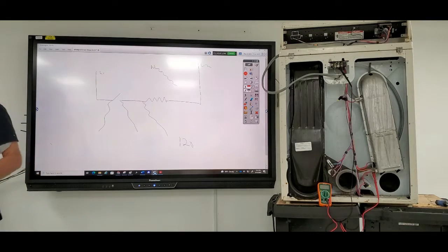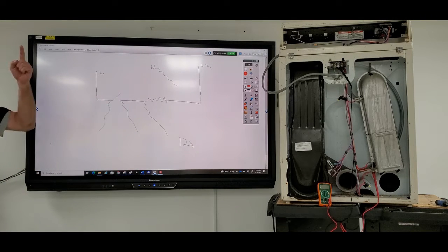Because how much power does it take to make that heater work? 240. You have line 1 and line 2 feeding everything. But now line 2 is further through the circuit than it's supposed to be, and it's still going to give you a voltage reading of only 120. It is not an accurate way to do any test.